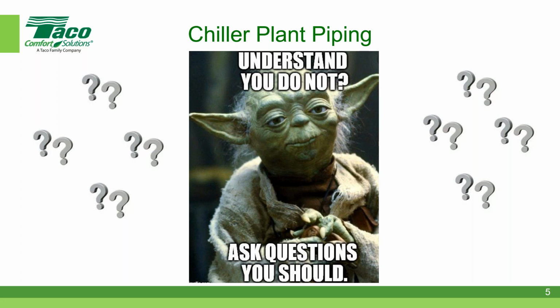There's one other question that we can cover in a short time. How do you deal with chiller cycling at low flows? Well, we're going to have to give a quick answer. Bypass, bypass, bypass. And controls. Yeah, as it turns out, with chillers short cycling, there's a whole series of problems to reconcile. We don't really have the time to go into all of those different issues, but I think to your point, Brett, properly sized bypass is the primary solution for keeping chillers from short cycling.